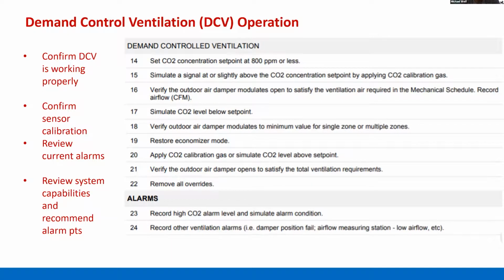And then finally, looking at demand control ventilation, I think a lot of people have heard the guidance here of disabling your demand control ventilation, making sure we can adjust that set point as low as possible so that demand control ventilation will in effect not kick in. But a few other things you can look at: if you're monitoring CO2 level in the space, that can actually be a pretty good indicator of your ventilation effectiveness, the effectiveness of your HVAC system, maybe in purging CO2 from the space.